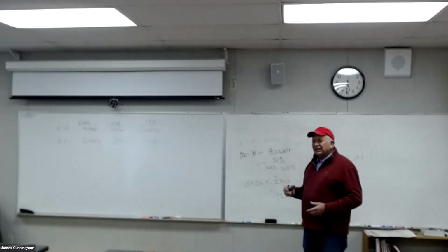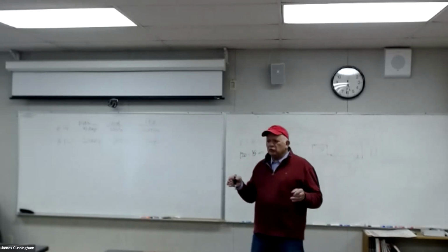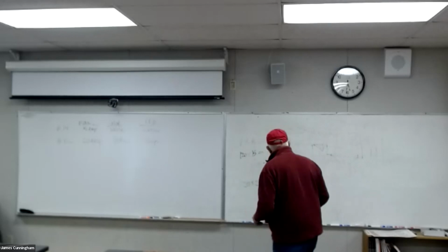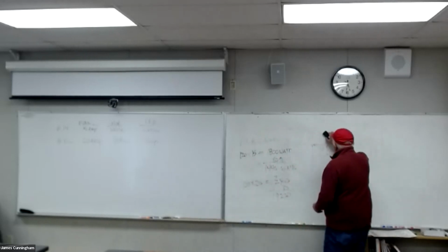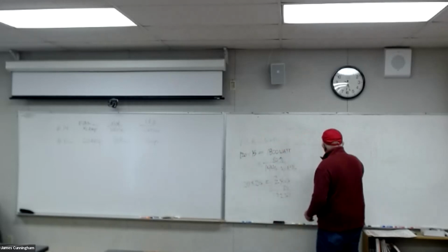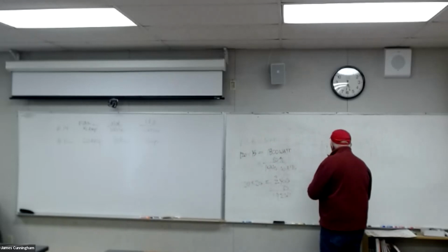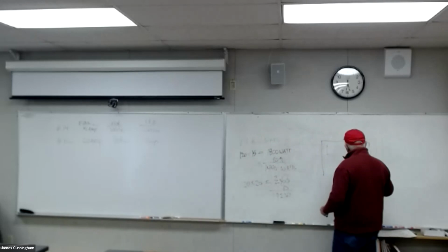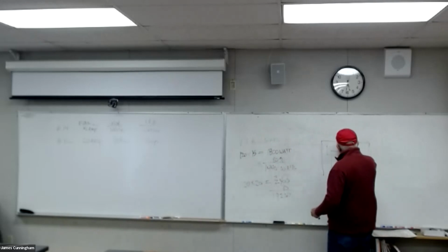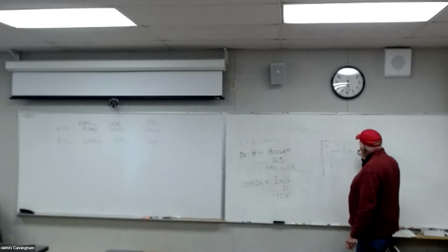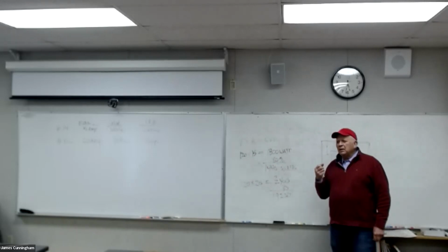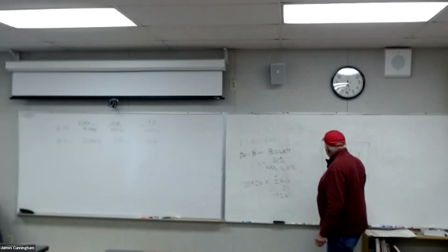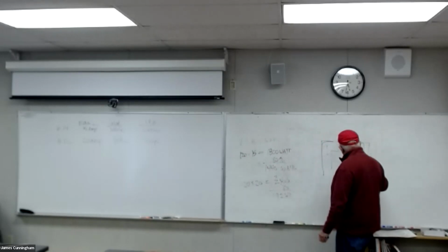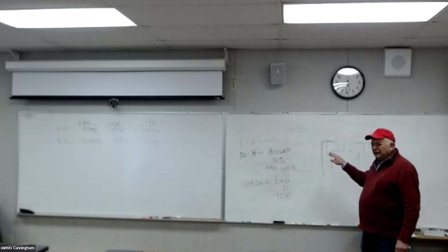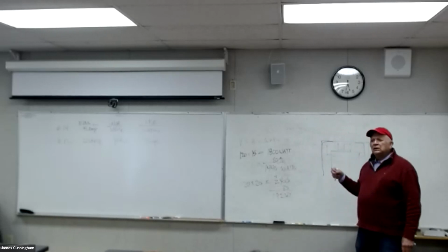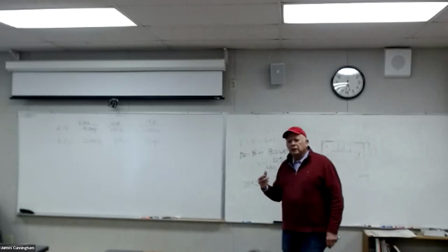Kitchens are a special situation because in a kitchen, you can't have more than 2 feet of counter space without a plug. You can't overload the circuit, so if I had a kitchen like this with counter space and here's my kitchen sink, the code says I have to have a minimum of 2 plug circuits on my counter. One circuit for plugs over here, and another circuit for plugs over here. Then I have to have separate circuits for the garbage disposal, dishwasher, refrigerator, and microwave. We'll get into that a little more.